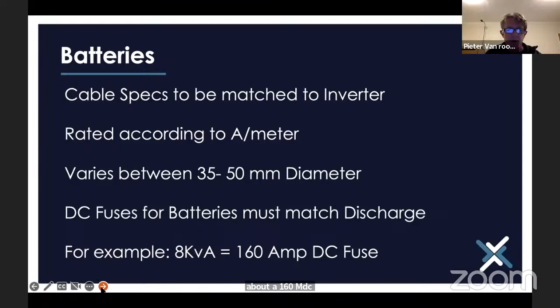DC fuses for batteries must match the discharge. It doesn't help if your fuse doesn't match, then it's going to blow all the time. For example, if you have an 8 kVA system, then about a 160 amp DC fuse would do you fine.